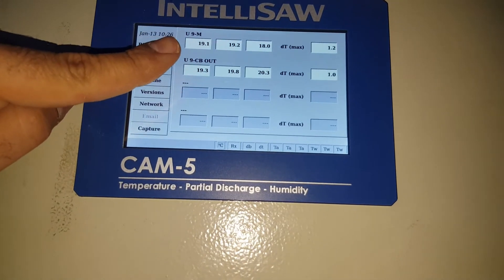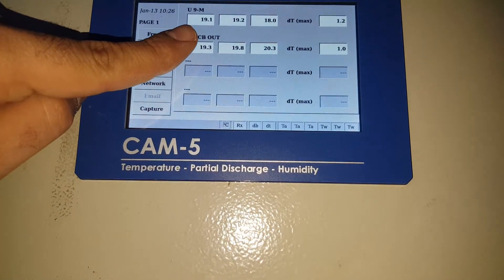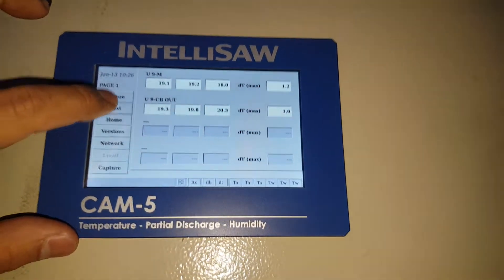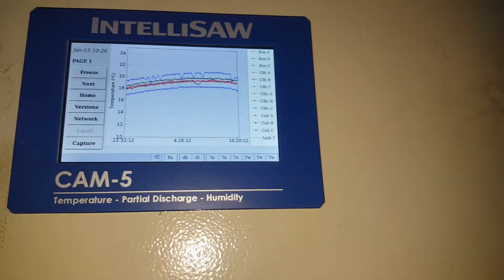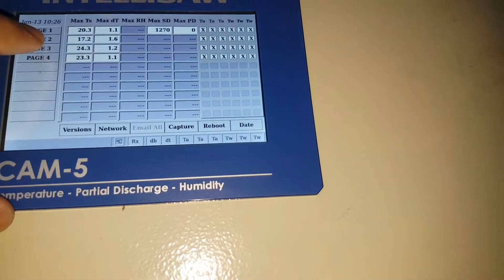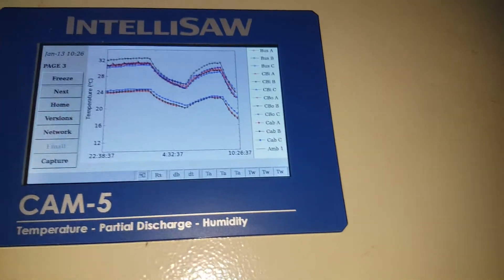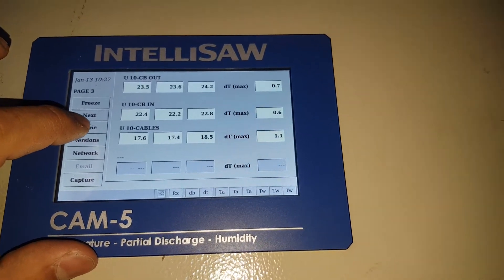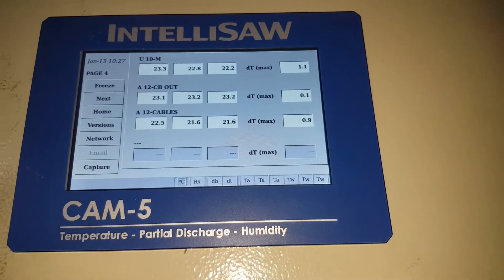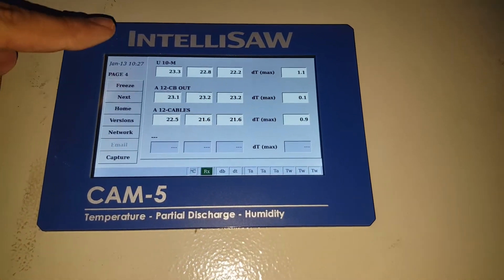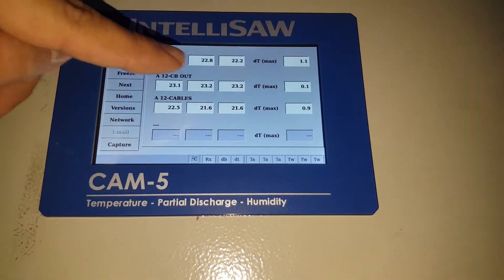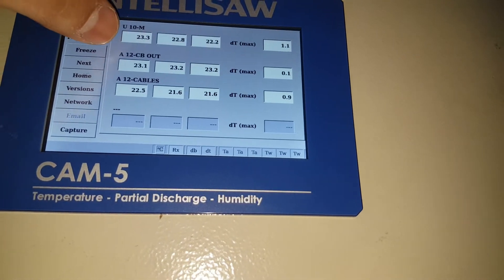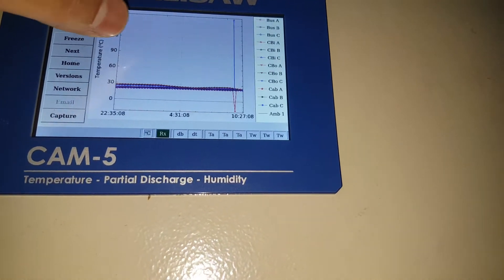The temperature for phases R, S, and T is shown here for unit 9 — a meter in the panel. We also have this curve showing readings over 12 hours. The temperature for each phase is for unit 10, another meter in the panel. This one is for auxiliary 12 CB out.